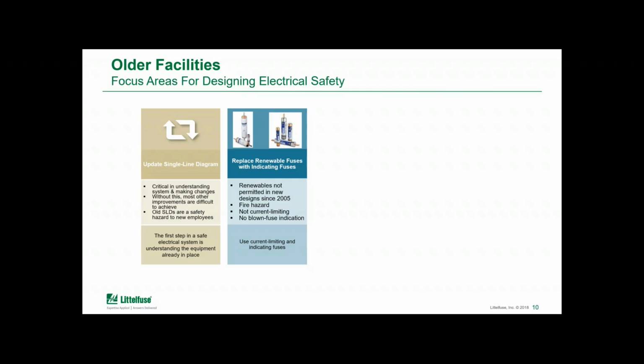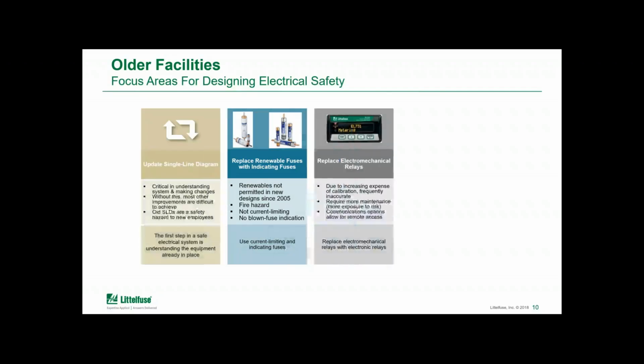you have renewable fuses, with newer fuse technology that is current limiting and indicating. Those products can provide better protection, particularly if you're comparing to the renewable fuses. If you're in a facility that's old enough, again, you might also have some older electromechanical relays. And these could be feeder relays, they could be motor relays, they could be overcurrent devices.